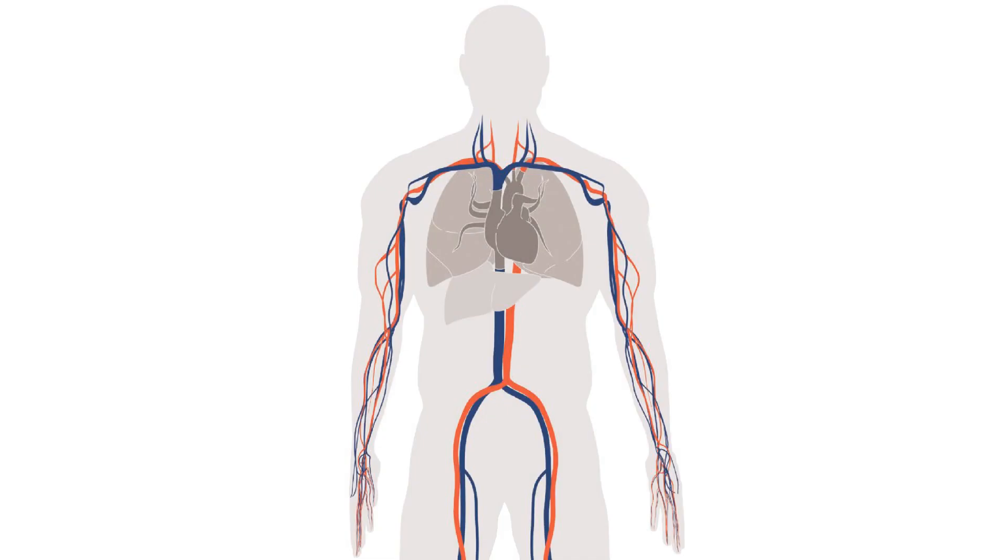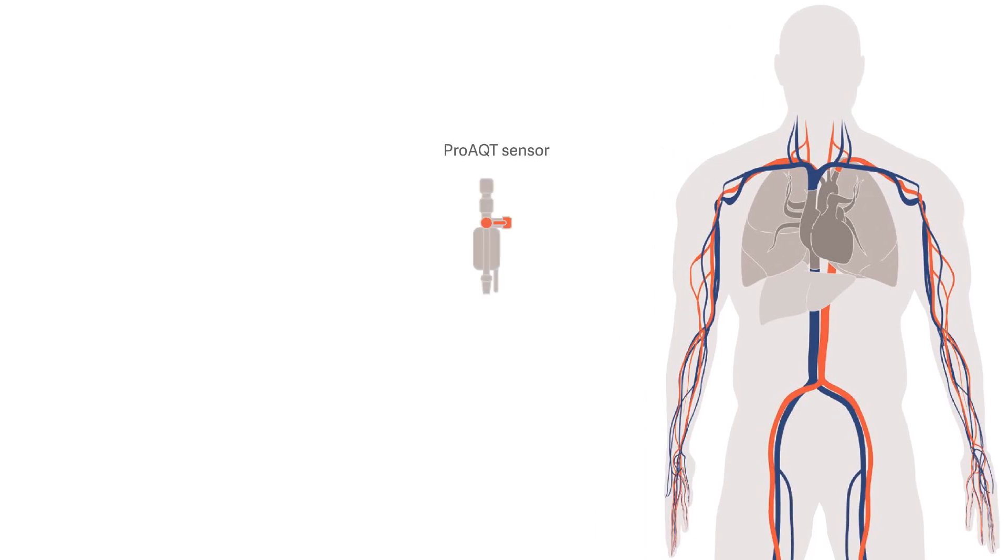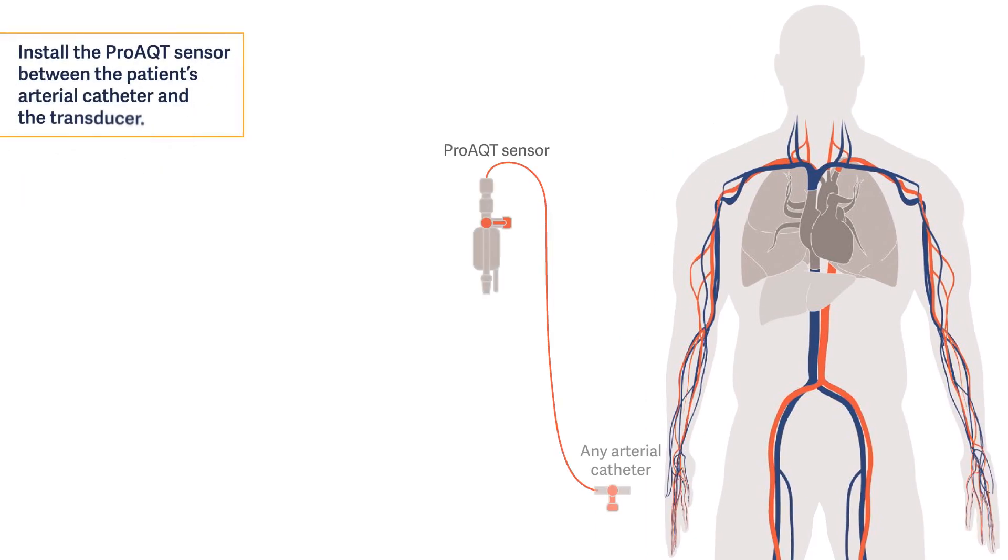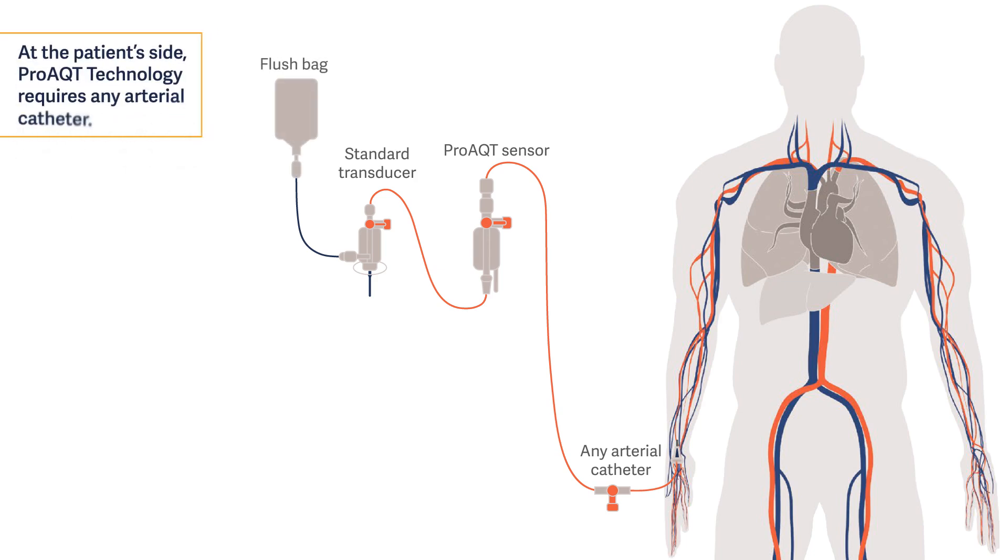To use ProAQT technology, properly set up its equipment. To set up the ProAQT sensor, install it between the arterial catheter and the transducer. It can be any arterial catheter. Prime the complete system. Connect the ProAQT sensor to the monitor.